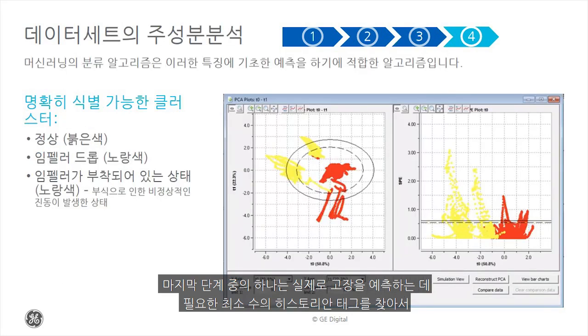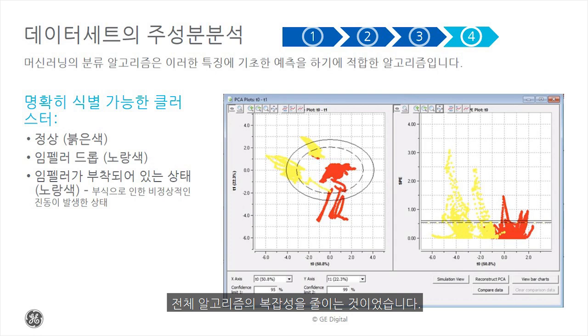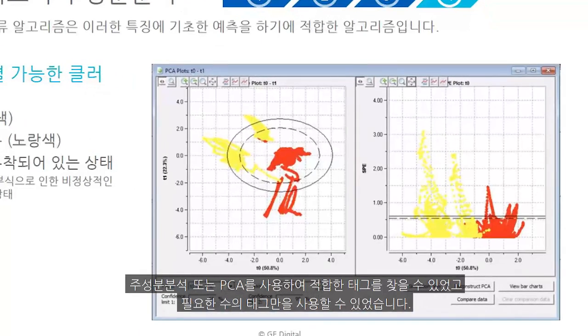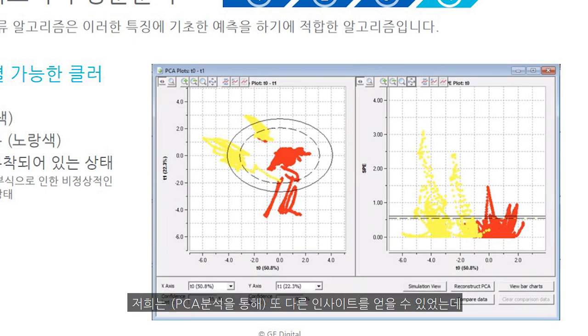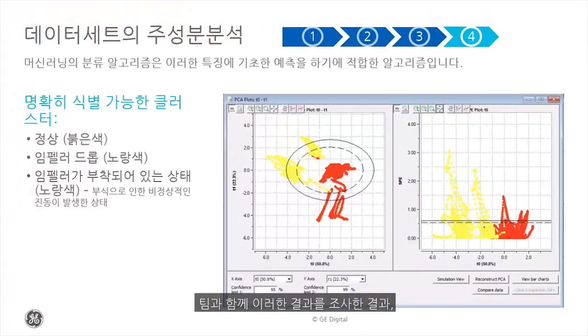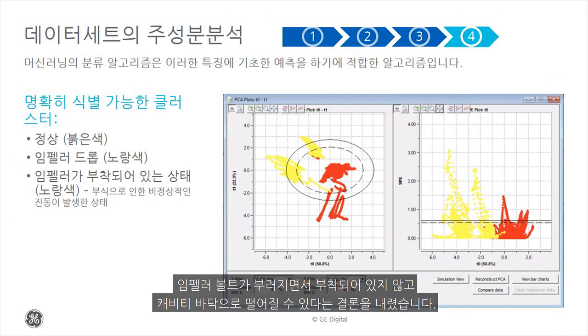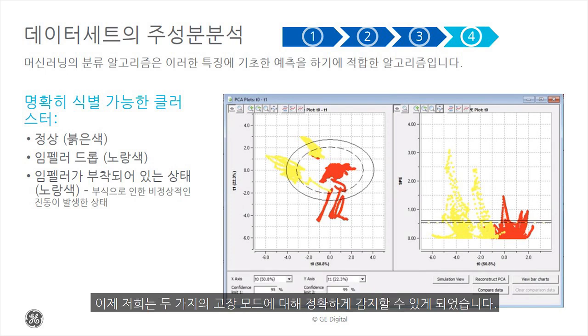One of the final steps in this process was to reduce the complexity of the entire algorithm by finding the minimum number of historian tags required to actually predict the failure. Using principal components analysis, or PCA, we found the right tags to use and the right number of tags. But we also gained a new insight. We learned that the failure data, painted here in yellow, was not the same failure mode repeating twice, but in fact was a completely separate failure mode altogether. After exploring these findings with the team, we concluded that sometimes when the impeller bolt snaps, it's possible for the impeller to fall to the bottom of the cavity rather than staying attached. So now we'll be able to accurately detect both of these failure modes.